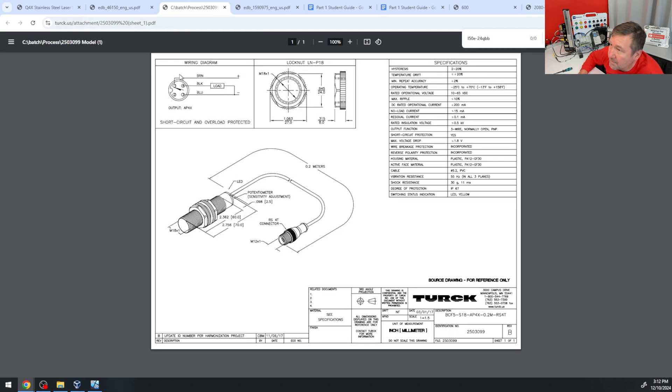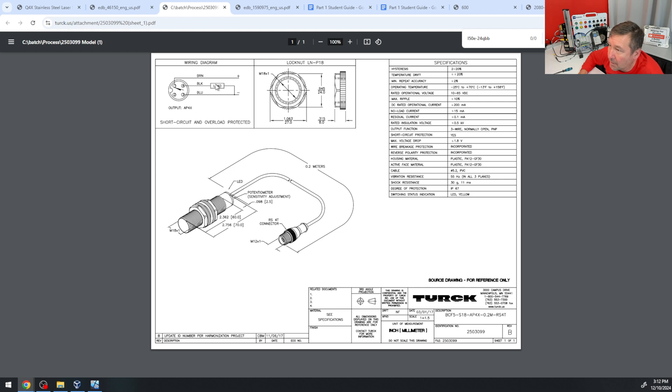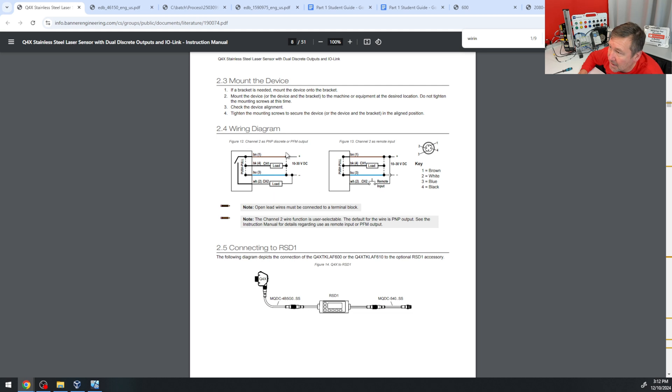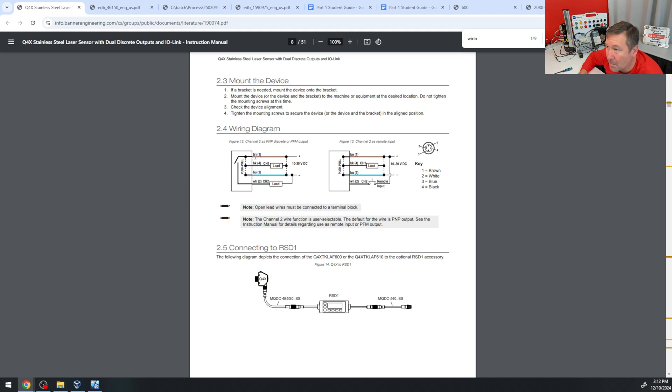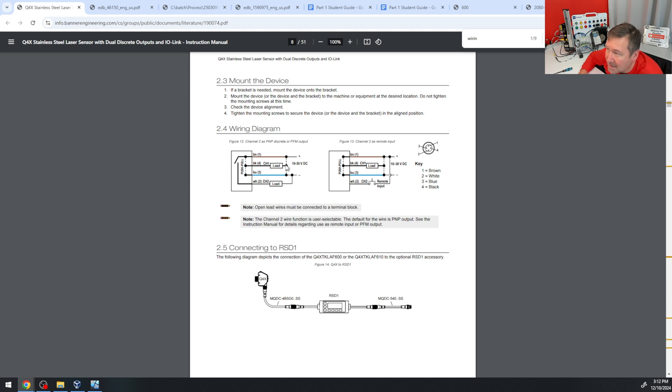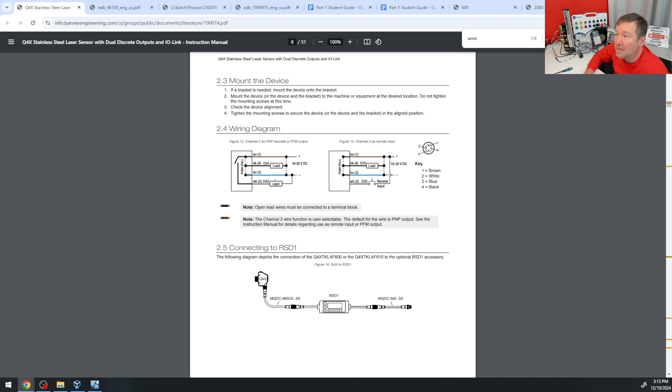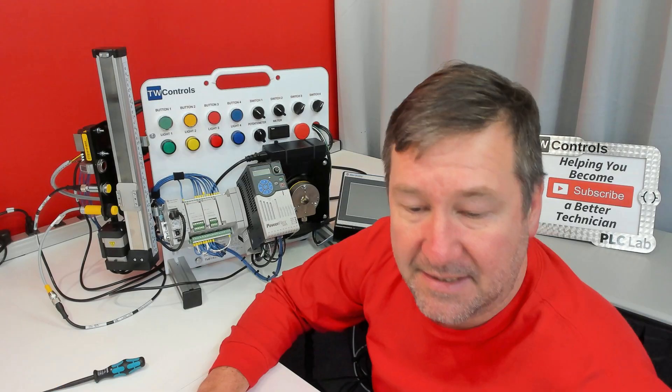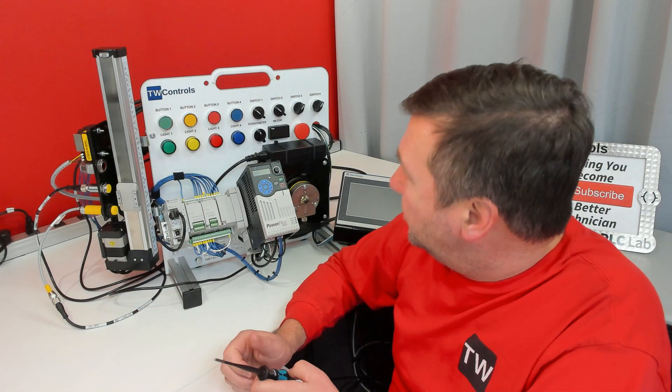And very similarly on the capacitive, we're going to have 1 brown B+, 3 blue B-, and then black will be our input, and there's that COM0 coming around. Now on this one, this one actually will automatically switch, basically what it means by push-pull. And you'll notice the wiring is going to end up exactly the same. Brown 1 is going to be our plus 24. Blue 3 is going to be the minus. And then black, pin 4, that's going to be our input. And then depending on where we put COM0, notice here's that COM0 wire actually, where we put it determines whether it'll act as a PNP or an NPN sensor.